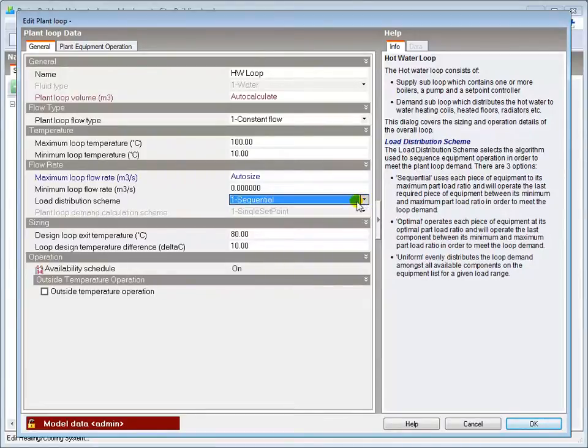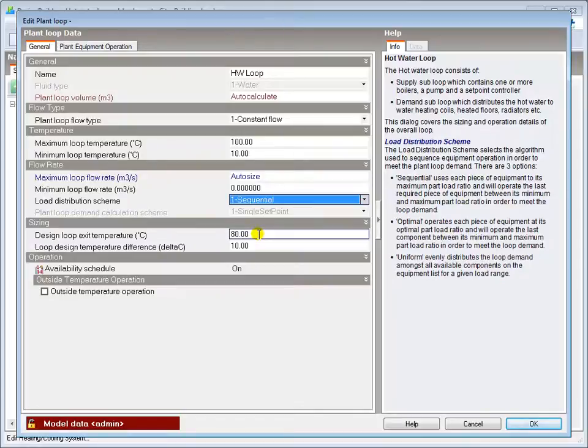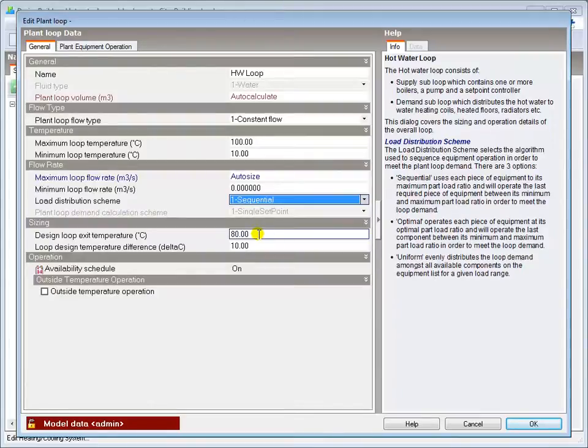The design loop exit temperature is the temperature at which the water is supplied to the hot water coils in the demand sub-loop. And the temperature difference is the temperature reduction across the demand loop.